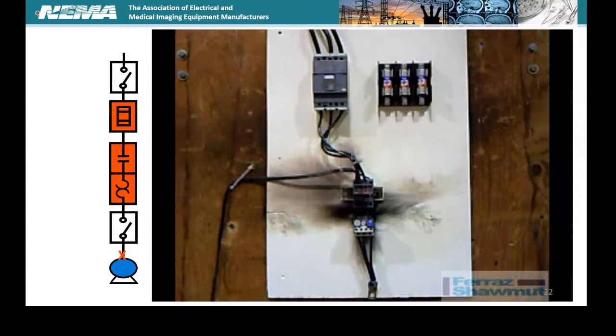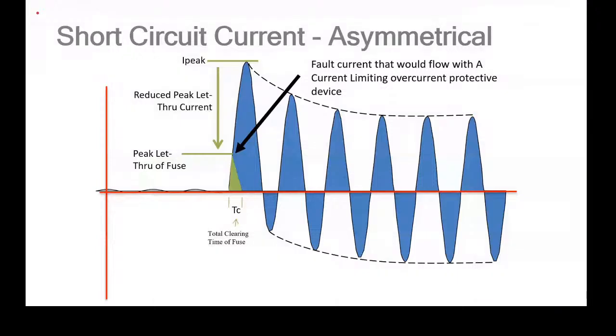Great. Okay. So let me go back to the slides I pulled, Tom, from your current limitation fuse presentation. And this shows a little bit of that asymmetrical sine wave you were talking about. Yeah. So what's really important is, if you remember, we talked about the asymmetrical waveform during a short circuit event. That first half cycle is a doozy, right? And the reason is because of the slope of that first half, that first line. When you go into a short circuit, the slope is very steep. It's like falling off of a really big pitched slate roof in Massachusetts, as opposed to a small, very lightly pitched roof. That first step is a doozy.